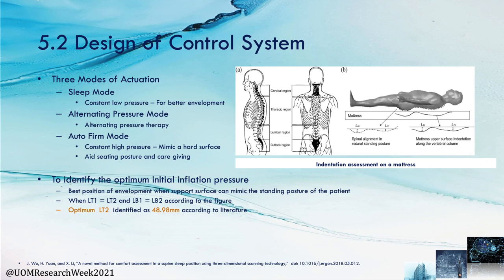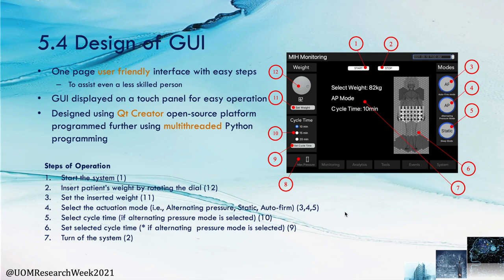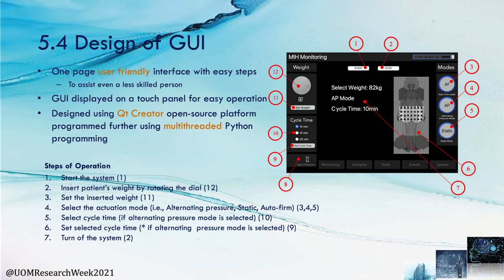Considering the third objective, the control system was designed with three modes of actuation: an alternating pressure mode, a sleep mode with no alternative pressure therapy, and an auto firm mode which maintains the maximum air pressure. The pneumatic system was designed using Festo fluid simulation to select the required pneumatic components to achieve the alternative pressure therapy regarding the predefined cycle pattern. A user-friendly graphical user interface was also designed to assist even a less skilled person to control the system.